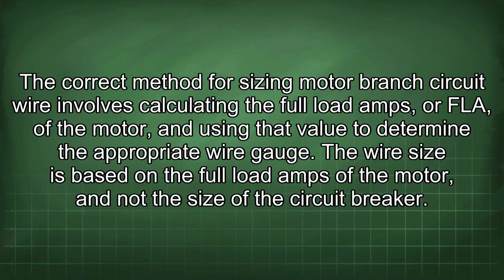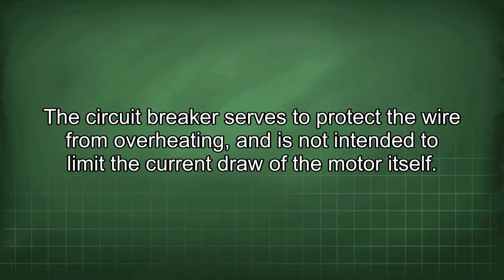The correct method for sizing motor branch circuit wire involves calculating the full load amps, or FLA, of the motor and using that value to determine the appropriate wire gauge. The wire size is based on the full load amps of the motor, and not the size of the circuit breaker. The circuit breaker serves to protect the wire from overheating and is not intended to limit the current draw of the motor itself.